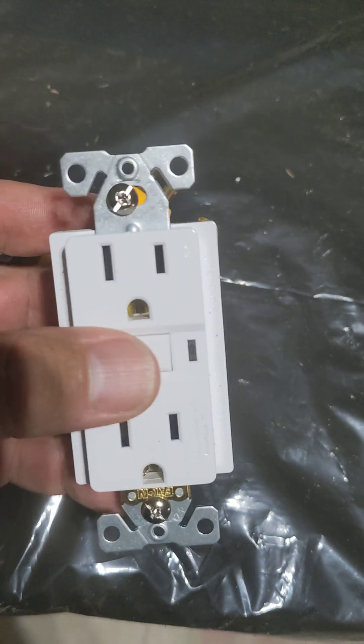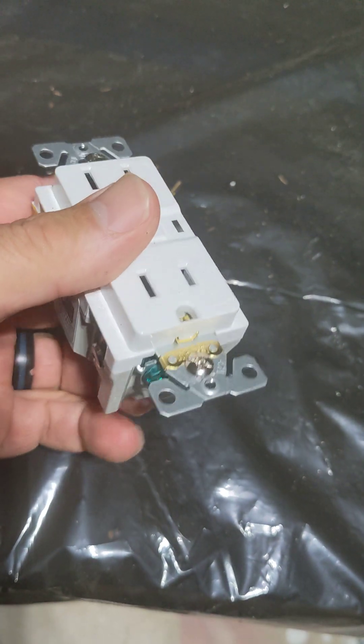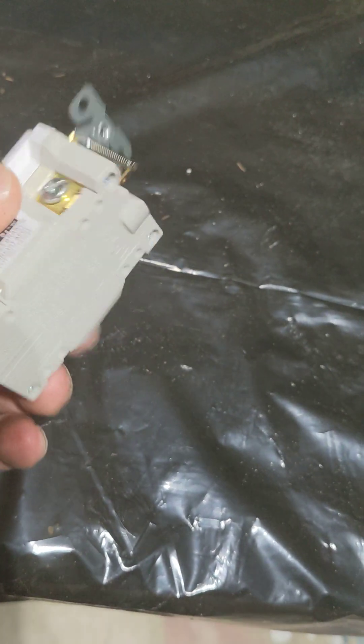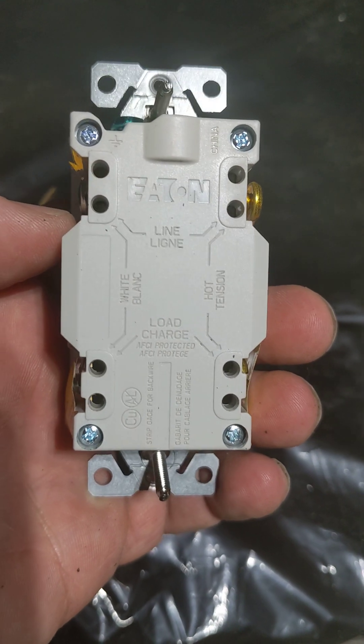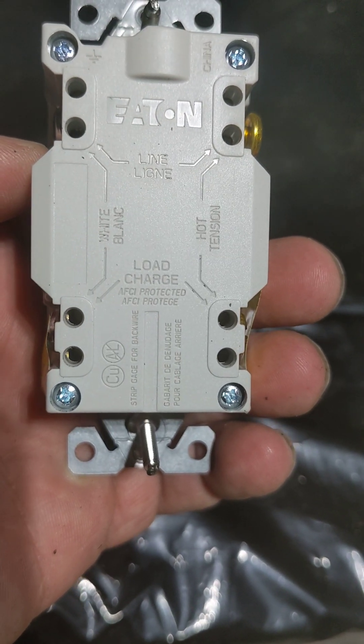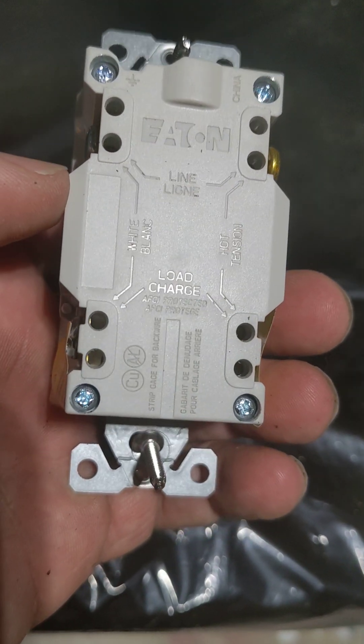Moving on — as you can see, there are two terminals that are exposed and then there are two that are covered by this yellow tape. It comes like that out of the box. The reason why is because the two that are exposed say 'Line,' and the two that are covered up indicate 'Load.' So the line is the power coming in, and the load is everything being protected under this AFCI.